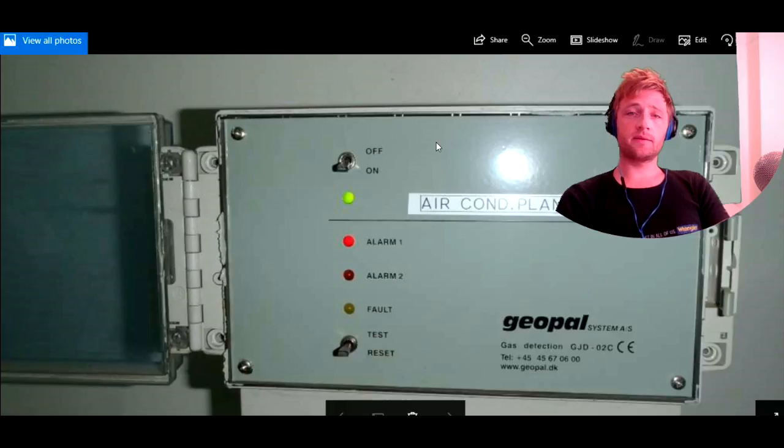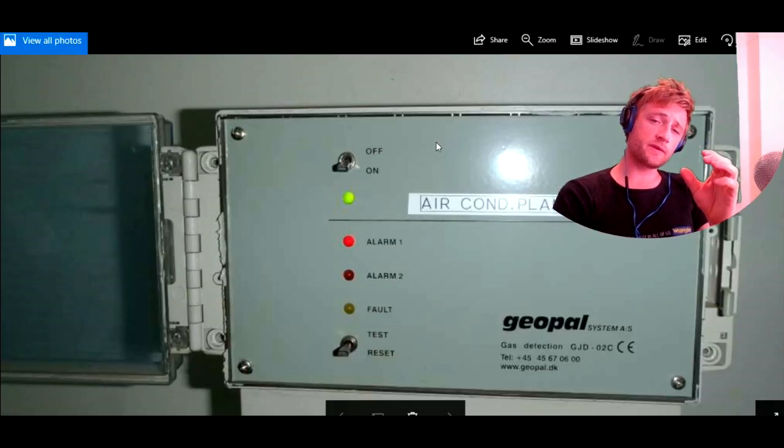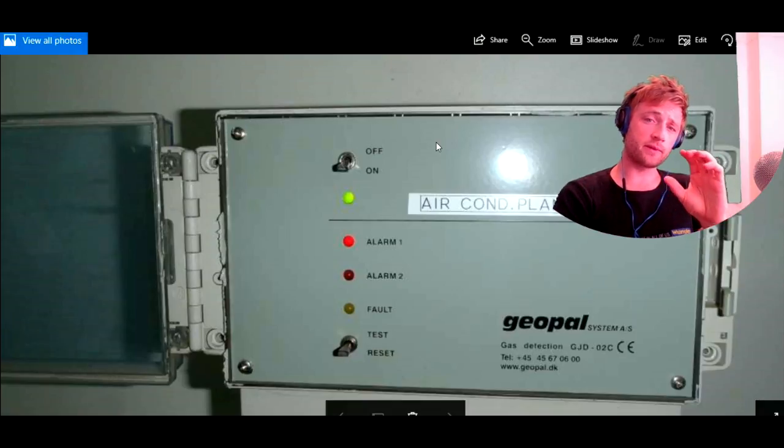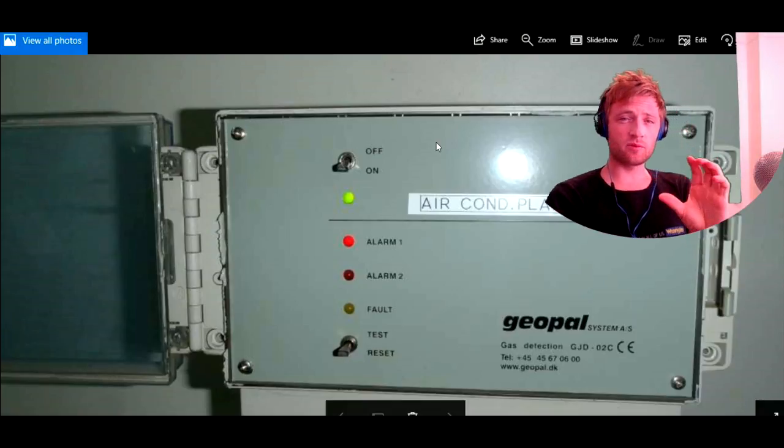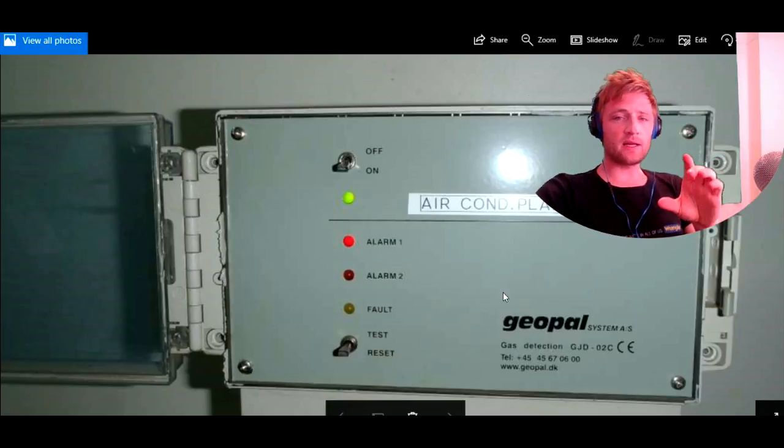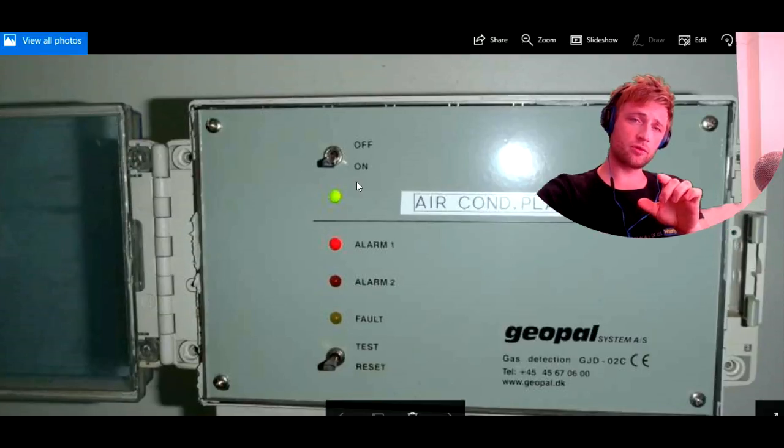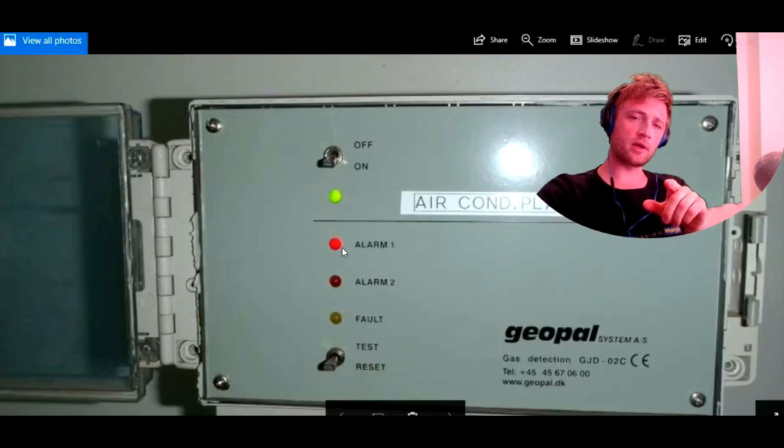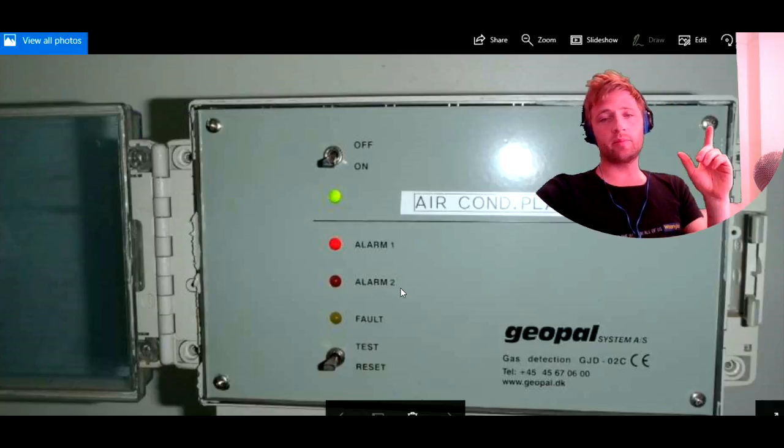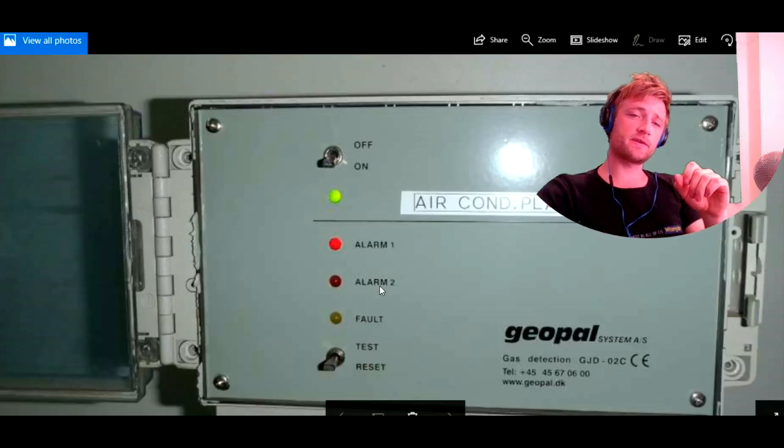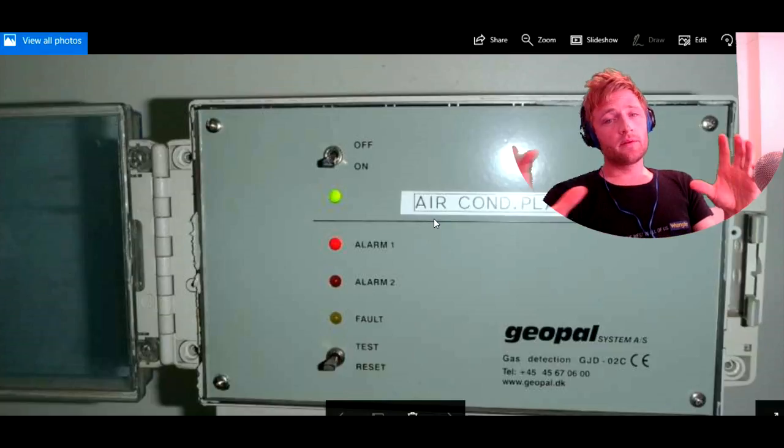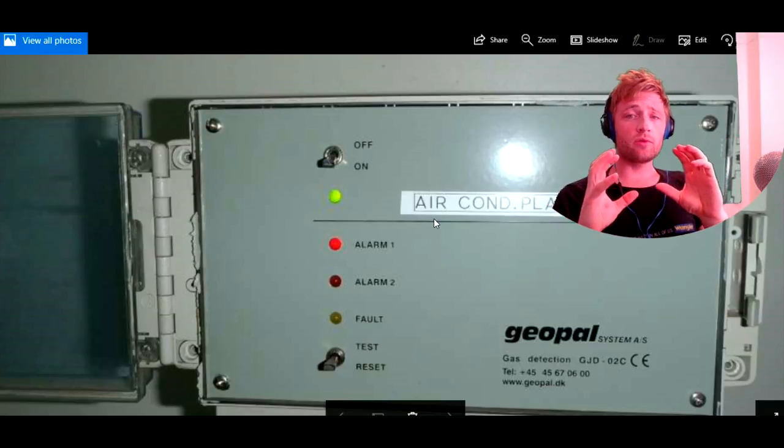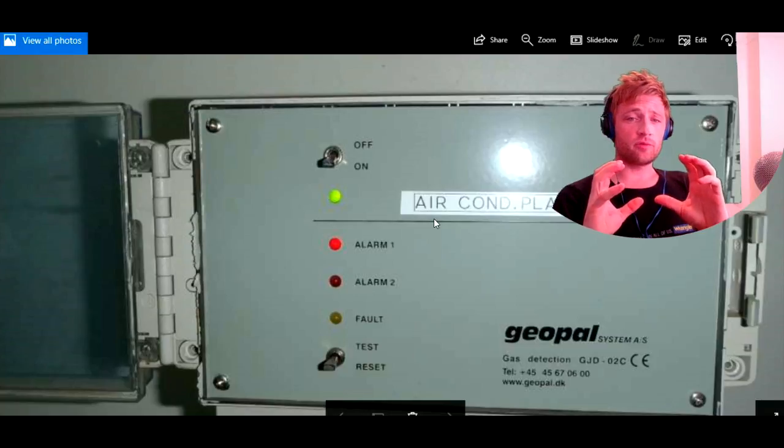And here today, what this video is speaking about is some small part of this plant—the gas detection system. As we can see here, we have the gas detection panel for air condition plant which is switched on. The selector here and we have green light. And we have, we can see here, two alarms: alarm number one and alarm number two. That means one of the alarms has been tripped.